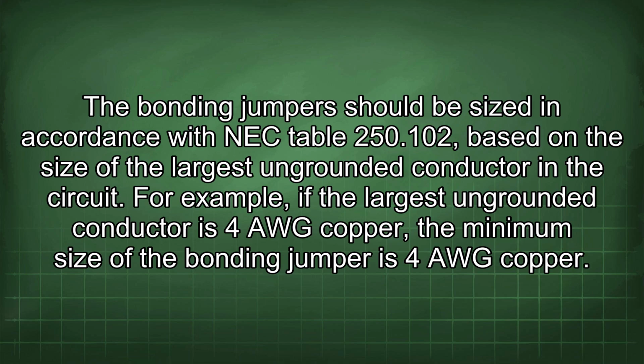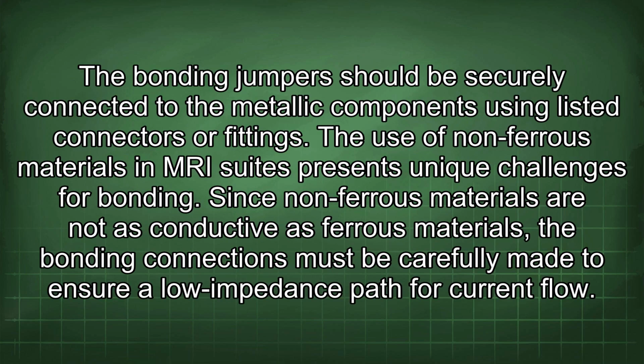The bonding jumpers should be sized in accordance with NEC Table 250.102, based on the size of the largest ungrounded conductor in the circuit. For example, if the largest ungrounded conductor is 4 AWG copper, the minimum size of the bonding jumper is 4 AWG copper. The bonding jumper should be securely connected to the metallic components using listed connectors or fittings.